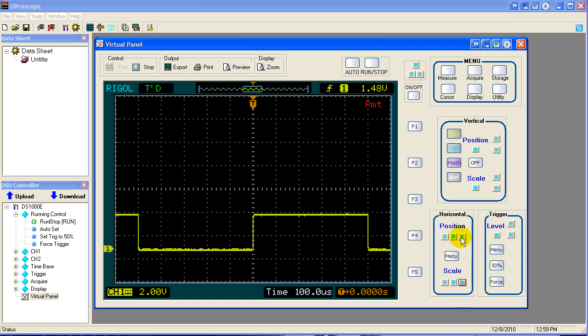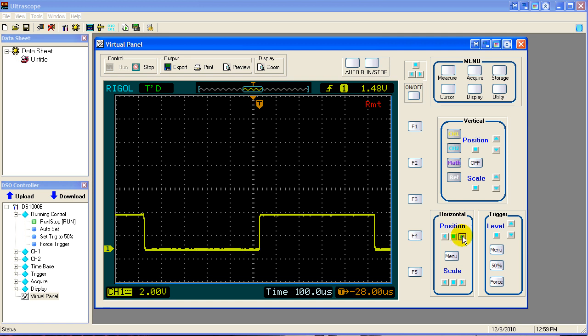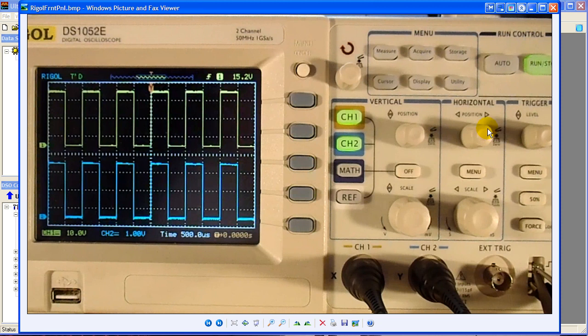We can also position the time base. In other words we can slide the waveform on the screen. So we can slide it one direction. And if we decide we want it back where it was originally, when you push on the position button, the horizontal position button, let's take a look at that real quick. The horizontal scale and the horizontal position button. We turn this button left to right. We can slide the waveform left to right. When we push on the button it takes it back to where it was when it was originally triggered.